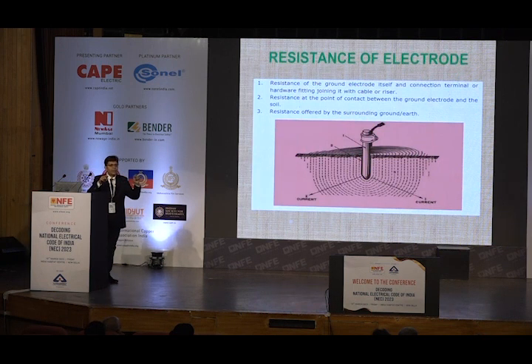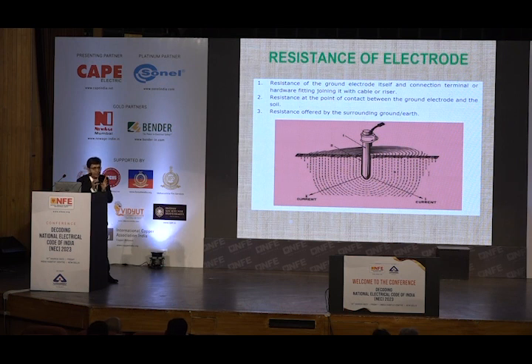At the end of your commissioning, you have to actually measure whatever you have designed and implemented, whether it is up to the mark or not. When I say resistance of the electrode or earthing system, it comprises the metallic part, the resistance of the point of contact between that electrode and ground, and the resistance offered by the earth. Out of the 3, the important part is the resistivity converted into earth resistance. Mother Earth plays a vital role in making the current flow. If your resistivity is already 100 ohm meter and you want to make it 1 ohm by inserting some magic electrode, that is not possible at all.